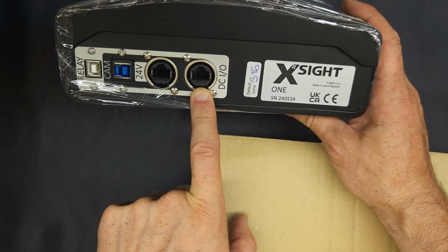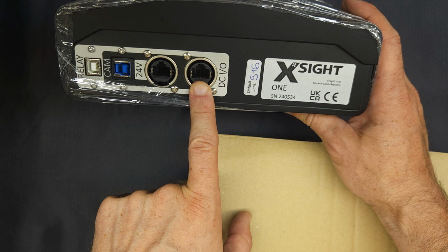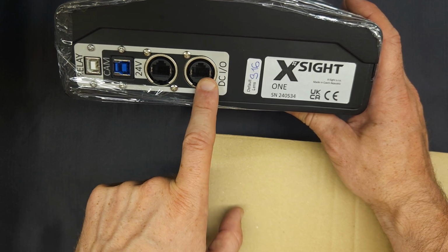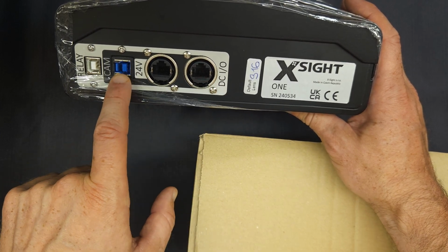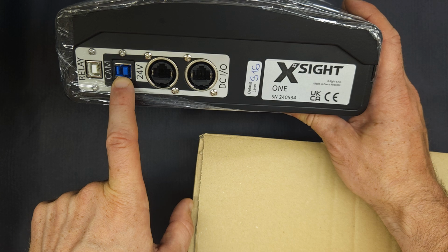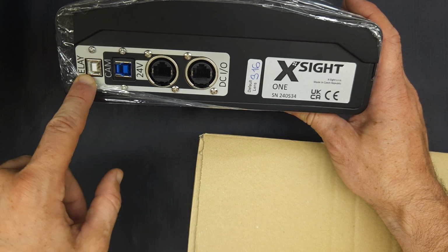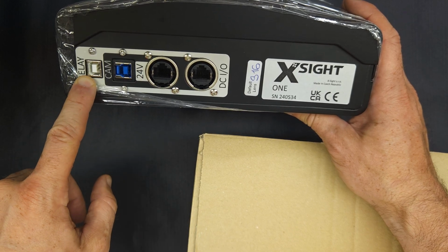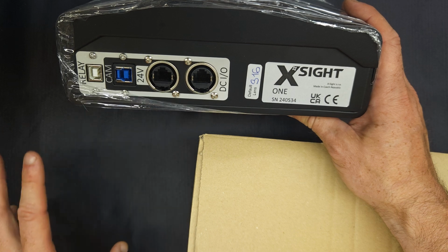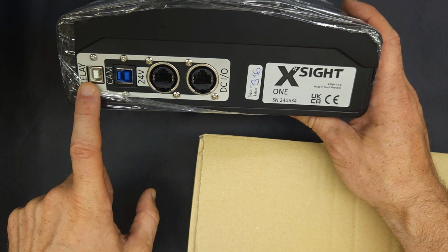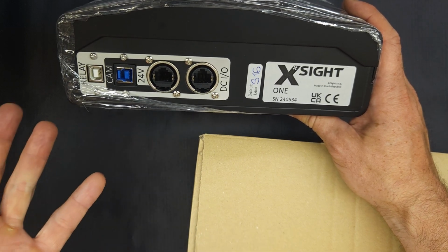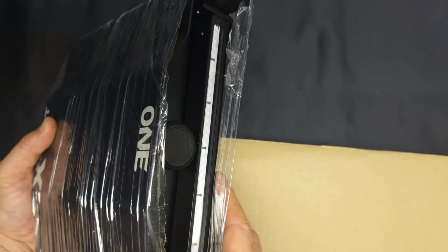When you hook this up to the universal testing machine, your I/O box is going to connect right here. This is the power for the camera, this blue one, and then this white one is the light relay switch. This will be used to turn the light on and off. If you don't want to use the relay, you can just leave the light on, so it's always on when the system is on.